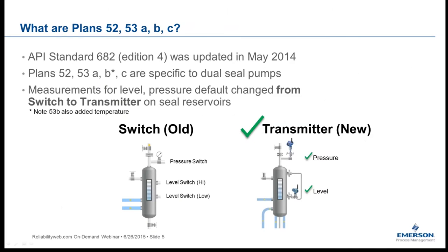The plans we're focusing on here are Plan 52 and Plans 53A, B, and C — all specific to dual seal pumps. The main difference between 52 and 53 is that Plan 52 is an unpressurized system and Plan 53 is pressurized. Looking at the artist renditions on the slide, Plans 52 and 53A look very similar at first glance but differ in the pressure at which they operate.